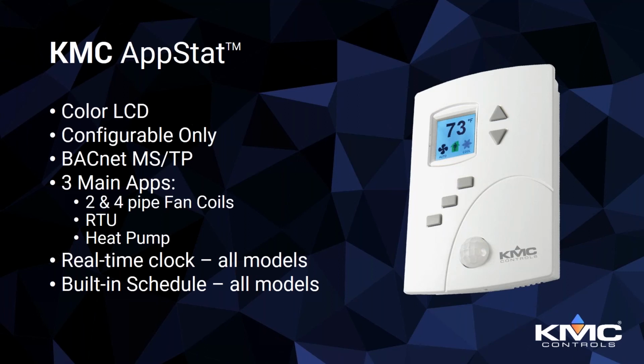So the one thing to remember with the KMC AppStat is that it stands for application-specific thermostat, right? So it's application-specific. You are choosing your model of AppStat based on what you're trying to control. Are you controlling an RTU? Are you controlling a heat pump? Are you doing the 2 and 4 pipe fan coils? That's something to really keep in mind, the application specific.